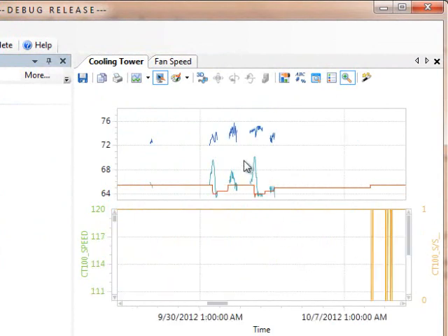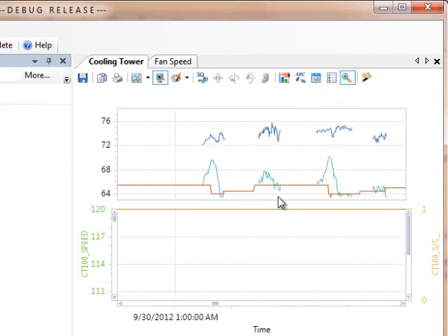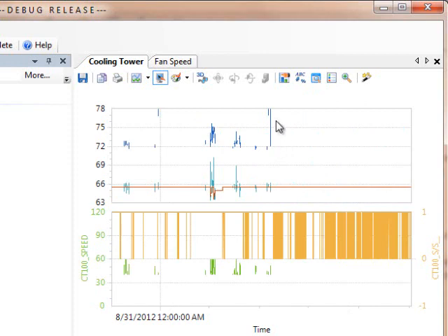So first set of values here appears to be, let's zoom in just a little bit more, appears to be in late September there, September 30, October 1, October 2, and October 3. And I can see the values as I mouse over them. For the Bay Area, that's not surprising. The supply temperatures here were around 70 degrees, 69, and 70 here. So that means the weather was probably warm enough to push the tower up against its limits.